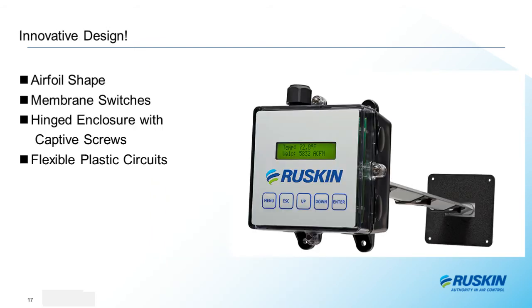What is innovative about this design? The airfoil shape is the only thing we kept from our previous design. Everything inside is new. Ruskin has invested 3 years developing this new product to make sure we addressed all the features our customers were asking for in an electronic air measurement probe. Accurate temperatures with the ability to offset up to plus or minus 3 degrees C, that's 5.6 degrees Fahrenheit, if necessary to match a test and balance reading.